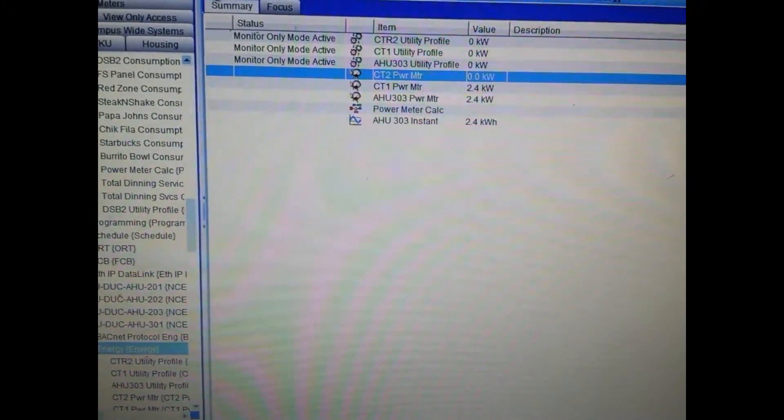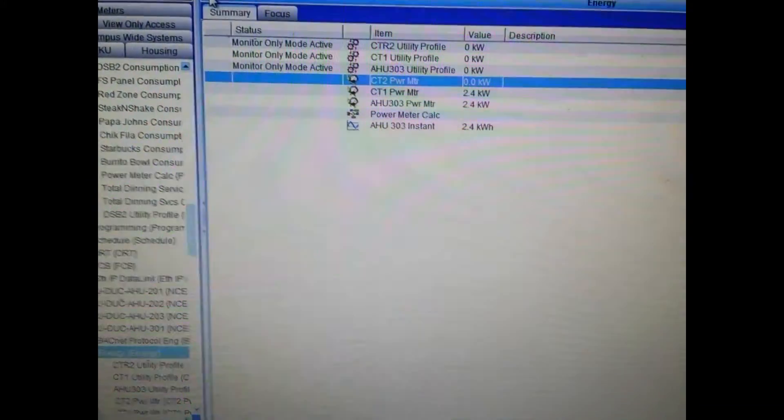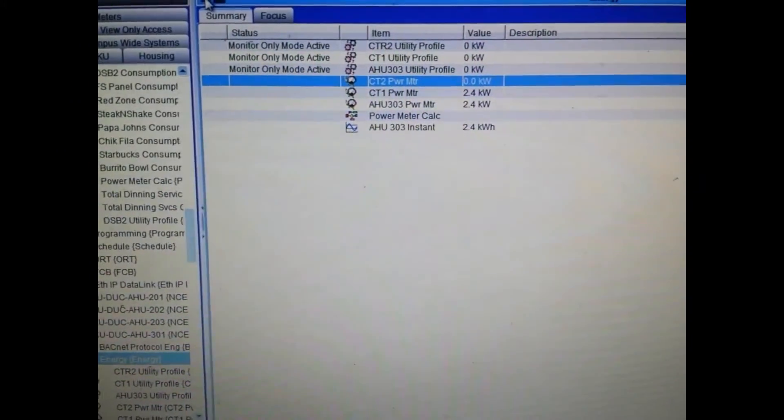The reason this meter was changed is because the usage from that meter is so light we're not getting an accurate reading. So changing the resolution should help to get an accurate reading from this meter.